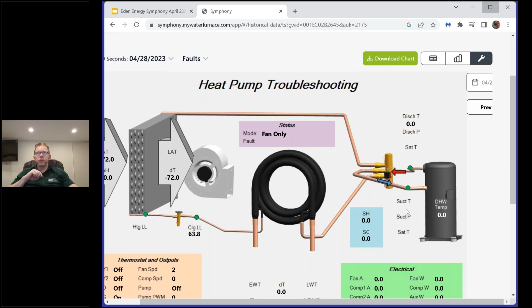So if we come up here and look at faults, we'll see if we can find a fault. This E99 is the homeowner resetting the unit. So case in point, if you have a lockout on a unit, you talk to the homeowner, say please don't reset the unit, just sit tight till we get there. Well, you can see how honest your homeowner is. This E99 fault for the longest time wasn't even in the manuals. Matt and I would scratch our heads going, what's an E99? Obviously, we eventually figured it out.